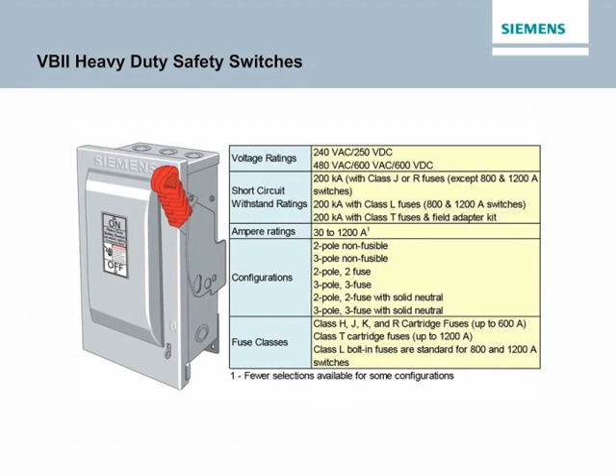The following configurations are available: 2-pole or 3-pole non-fusible, 2-pole 2-fuse, 3-pole 3-fuse, 2-pole 2-fuse and solid neutral, 3-pole 3-fuse and solid neutral. Fusible switches will accept the following UL class fuses: Class H, J, K, and R cartridge fuses for switches up to 600 amp, Class T cartridge fuses for switches up to 1200 amp, and Class L bolt-in fuses are standard for 800 and 1200 amp switches.